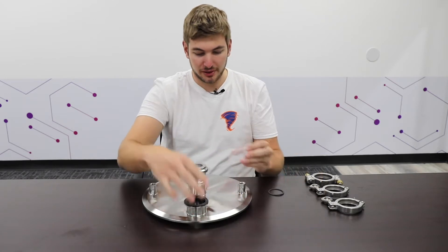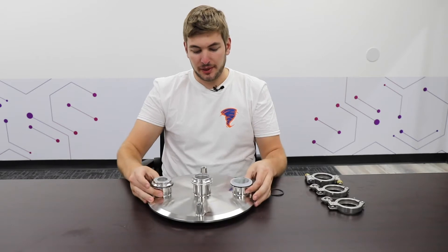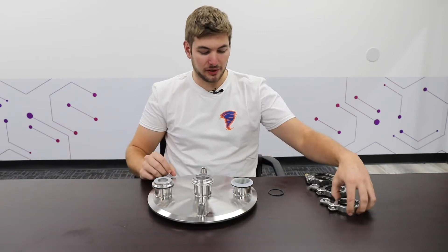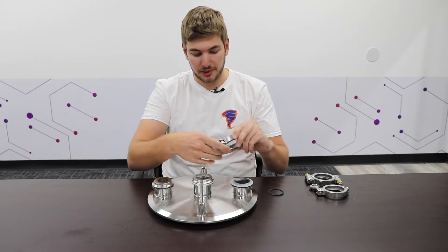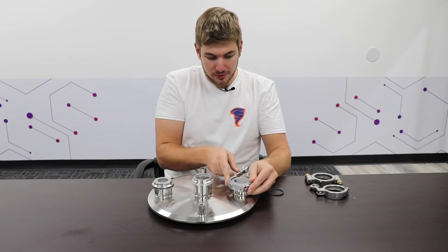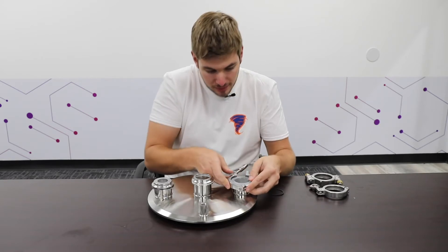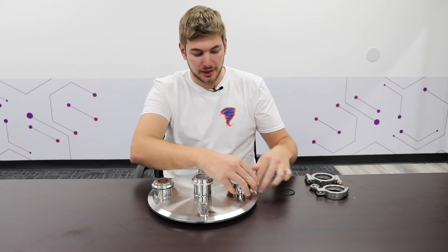And now I have my polycarbonate sight glass. These three options go on fairly similar, and you can use the same clamps for all of them. This is a low-pressure clamp, and I have a high-pressure clamp over there as well. This goes right around the sight glass.